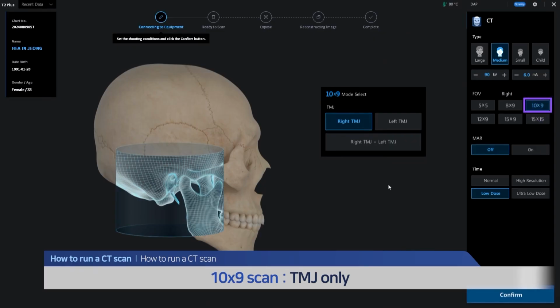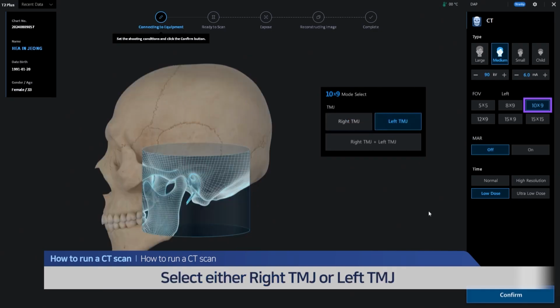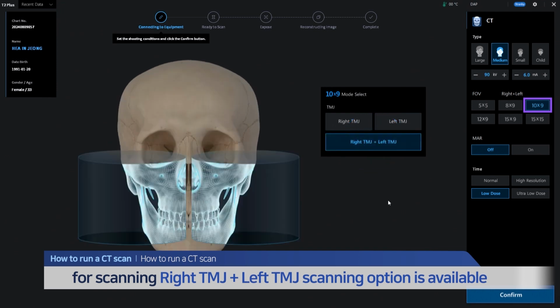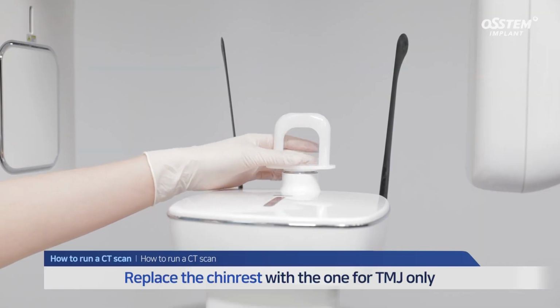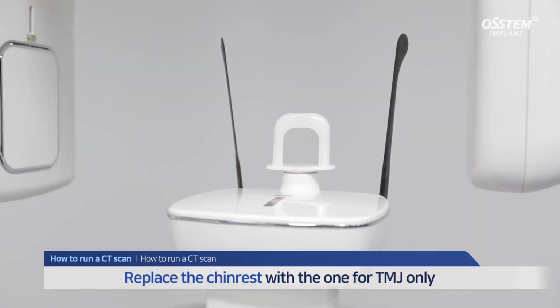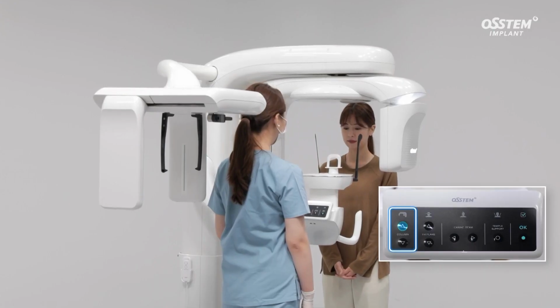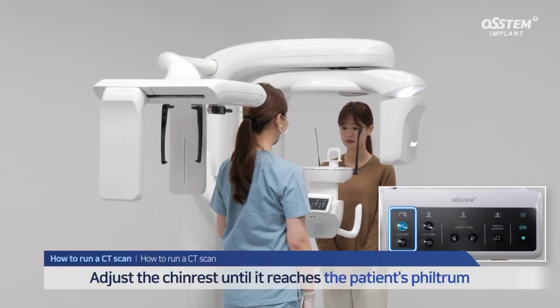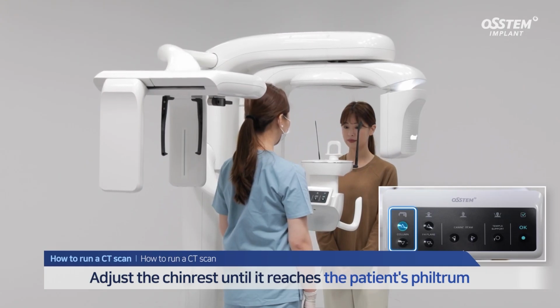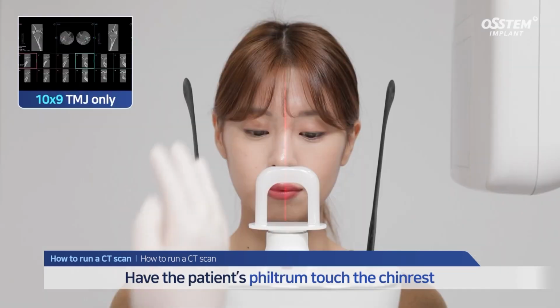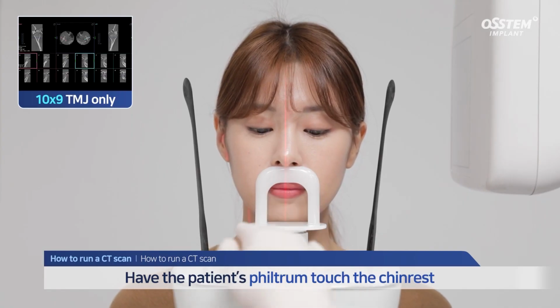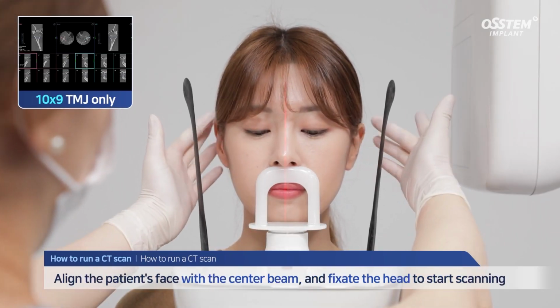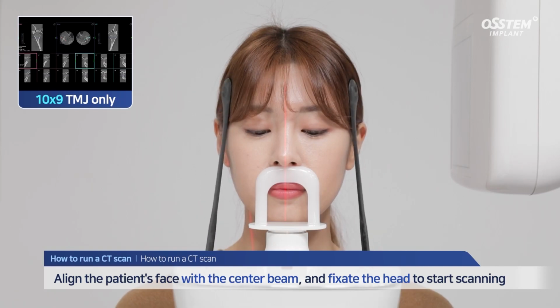10 by 9 scan is used for TMJ scan only. You can select either right TMJ or left TMJ for scanning, or scan both TMJs at once. Replace the chin rest with the one that is only used for TMJ. Adjust the height with the column up-down button so that the chin rest reaches the level of the patient's philtrum. Have the patient's philtrum touch the chin rest. Keep the center beam to the center of the patient's face. Then, fixate the head to start scanning.